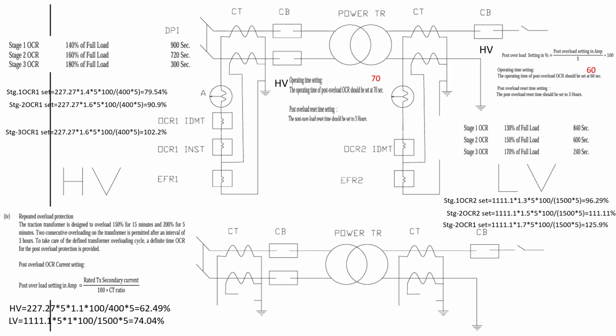And again, we know that with the CT and PT we are reducing the current and voltage for use in the panel board, where the operator can operate it within safe limits. Otherwise, you cannot directly operate with such a huge amount of current and voltage. So a 110 volt battery system is used, and we use an auxiliary transformer to step down 25 kV to 110 volt for the battery charger. Through this, DC is generated through a rectifier, and we charge the batteries and also use it for the relay protection as a DC supply.